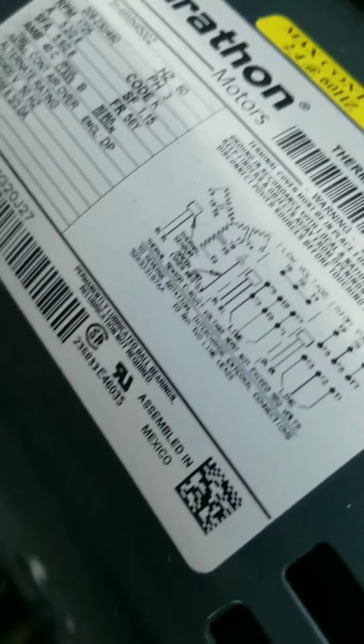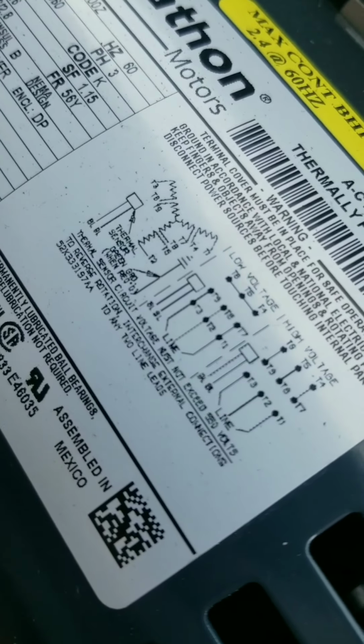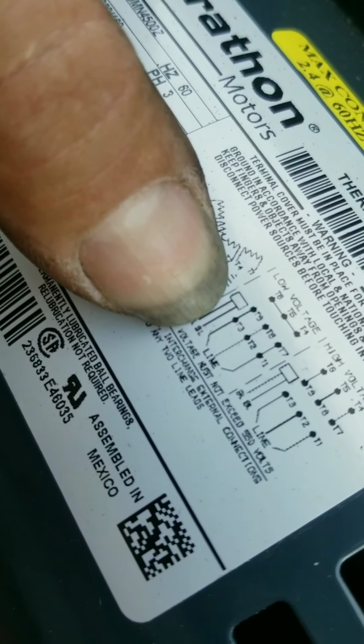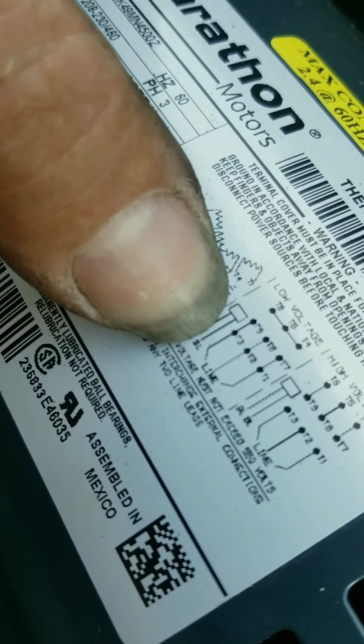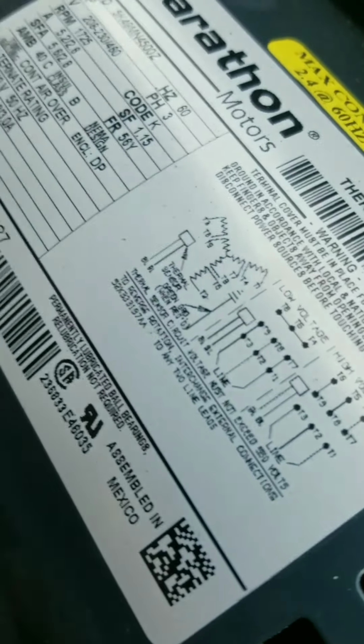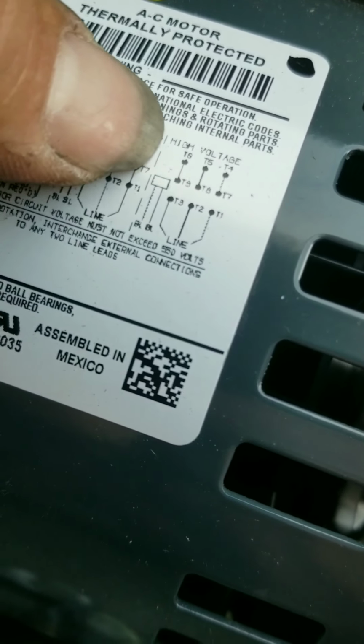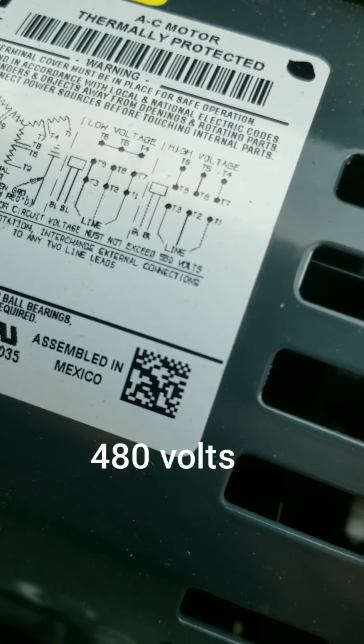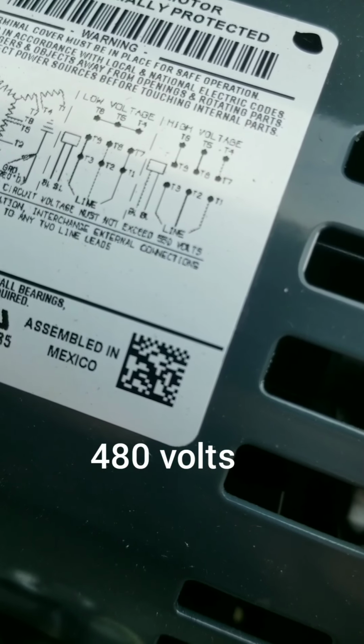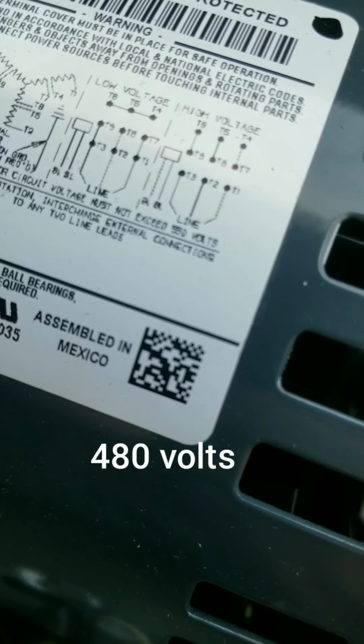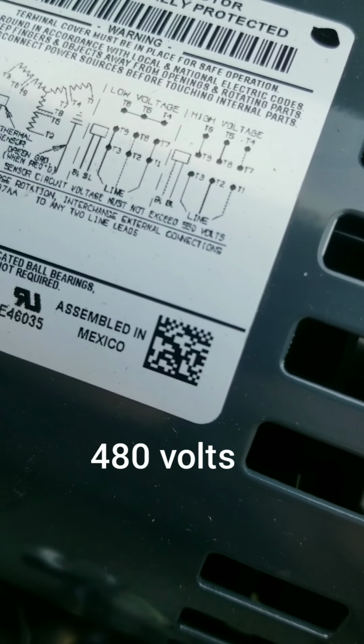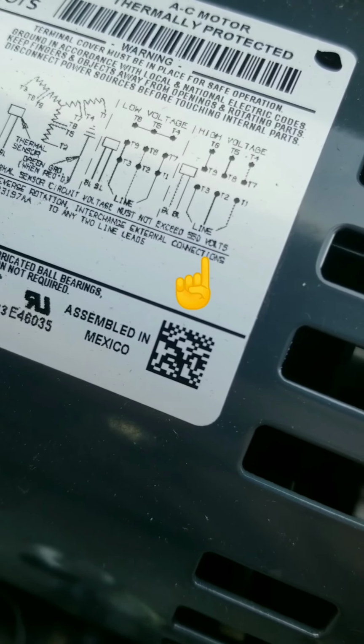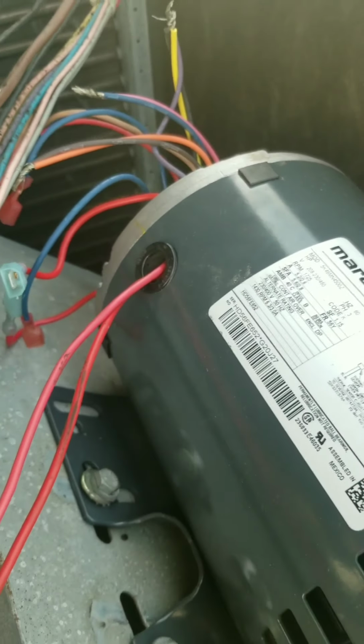You always want to be aware of your wire diagrams. These come wired for low voltage. So T1 and T7 is the line. T2 and T8. You see T1 and T7 is together. So we're wired for low voltage. We need to be wired for high voltage. So T4 and T7, T5 and T8 is going to go together, T6 and T9, and then T1, T2, and T3 is our line voltage coming in. So we're going to redo our wiring, and then we'll get this guy turned on.